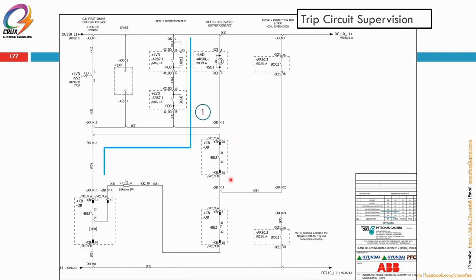But the schematic is actually already ready. If we want to monitor in the breaker open condition, we just have to do some rewiring and choose the right breaker status, open or closed. Okay, that's on the trip circuit supervision. So this circuit shows that the trip circuit supervision is only monitoring the healthiness of the trip circuit when the breaker is in closed condition, through this internal resistor plus TCS1, then going directly through the coil through BB2, normally open, but it will be closed during the circuit breaker closed condition. So it monitors not only the healthiness of this coil, these contacts and these internal resistors, but also the DC 110 supply and also the negative.